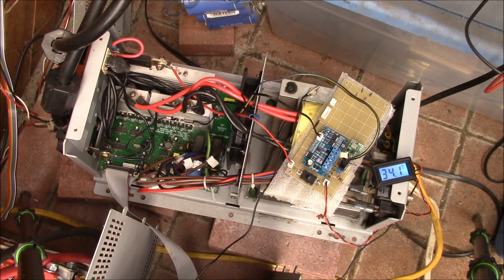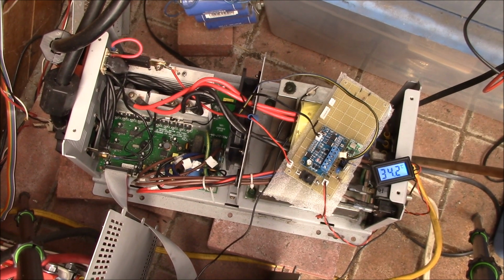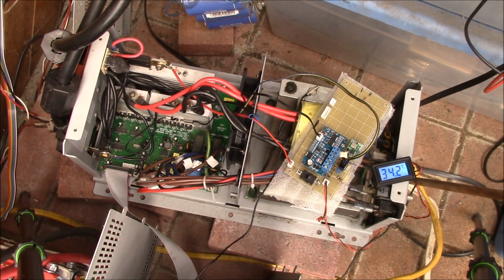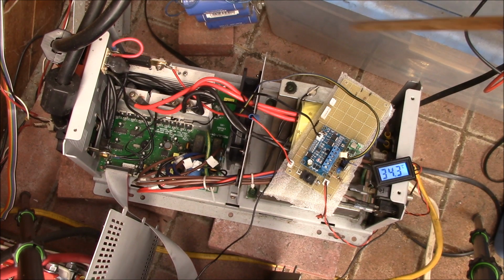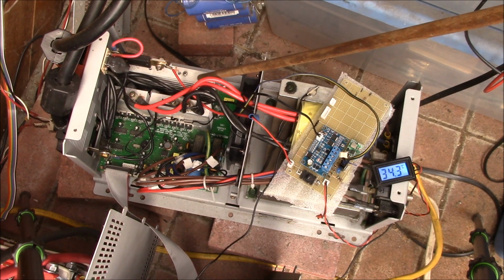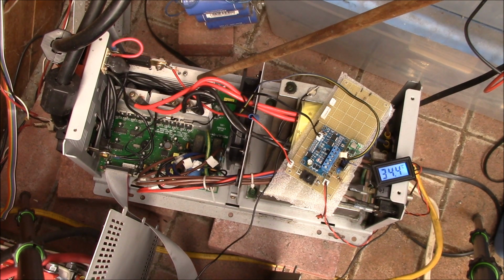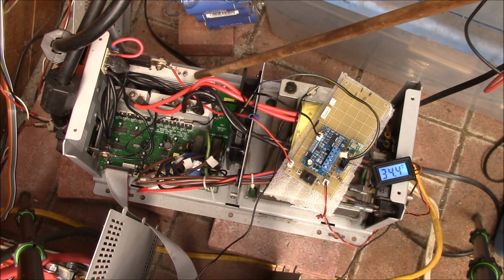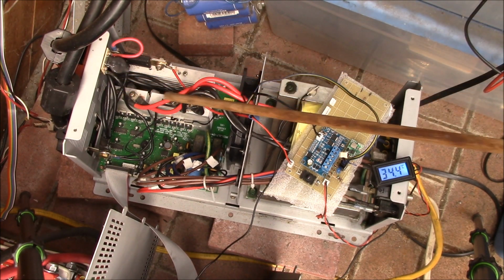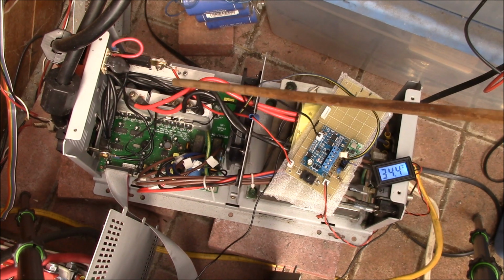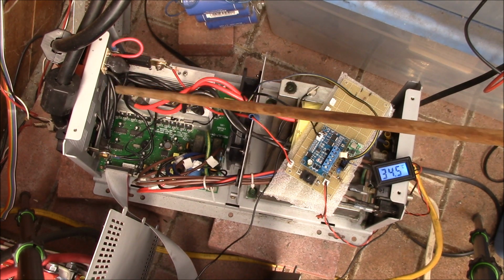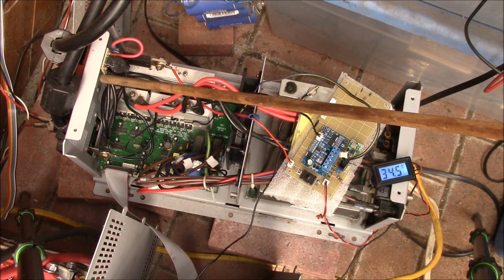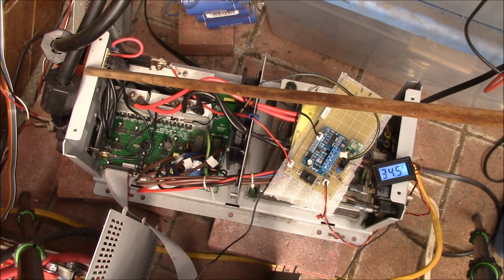It's basically a UPS, so it'll run just like a regular UPS. If I were to plug this cable into the wall right now, it would turn off this part of the inverter. It would no longer be generating a sine wave, and instead it switches these MOSFETs into a battery charger mode, pumping power backwards into the batteries.